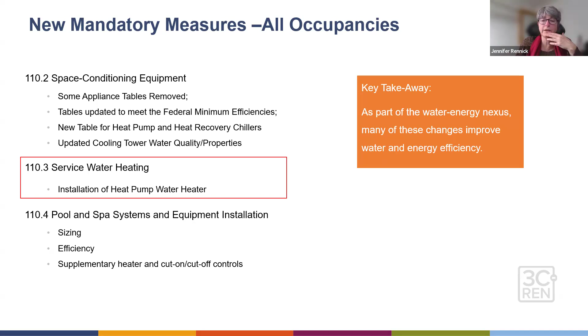We're going to just take a look at the service water heating for today. Under section 110.3, service hot water, section C is the installation, and we had 6 topics that dealt with mandatory requirements for heat pump water heaters, but now we've added a 7th, specifically the air source heat pump water heaters installation. Some of these were part of other parts of the code here and there. Now they've pulled that. It's all here, plus new stuff as we learn more and more about how to work with heat pump water heaters.